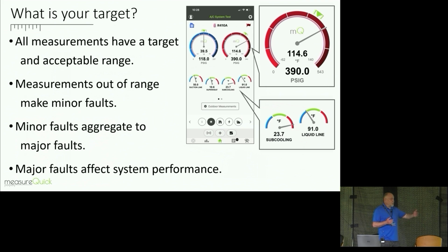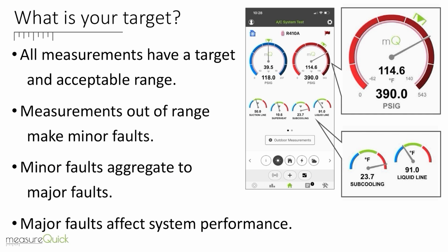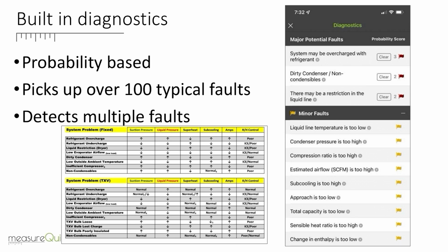If you're hooking up gauges to a machine and you don't know exactly what the pressure should be before you hook the gauges up, why are you even measuring them? What difference does it make, right? Yet most of our industry, nobody's ever taught us how to actually calculate what those readings should be. And MeasureQuick's got all those targets in there already tied in, so it'll do all those calculations for you. We pick up all the minor faults. So what we're doing here is picking up all the minor faults to aggregate into major faults, right? So it's got your built-in diagnostics. You've all seen this diagnostic chart before, and it's all probability based, but we've taken this and expanded it out to over 100 different faults. So all these little yellow flags at the bottom are minor faults that aggregate into your major faults.